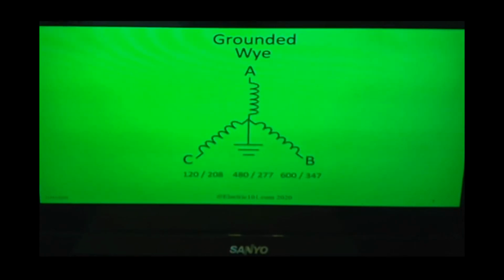So grounded delta, they're everywhere. Now, the most common circuit you're ever going to see is what's called a grounded Y. This is usually going to be the secondary side of the transformer, three phases. The center point of the transformer is grounded to earth. Okay, and from there, once it's grounded, this is where the neutral wire comes from.